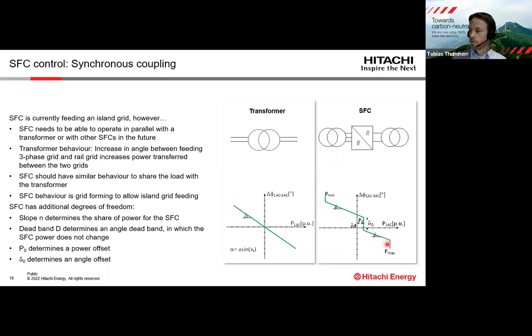And then we have additional degrees of freedom. We can introduce an offset in the angle as well as in the power. So we can shift the curve in either direction. And we can introduce a dead band here in the middle, and we can choose how big this dead band is. This characteristic gives quite a lot of degrees of freedom to set the behavior of the SFC. So for example, we can choose the dead band in a way that in a certain range, the SFC just supplies continuous power or zero power, and only the transformer reacts to changes in the angle difference.